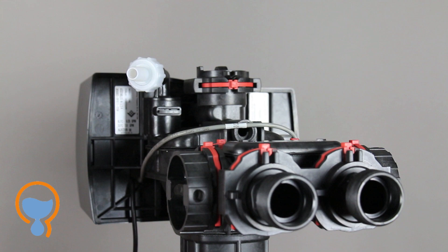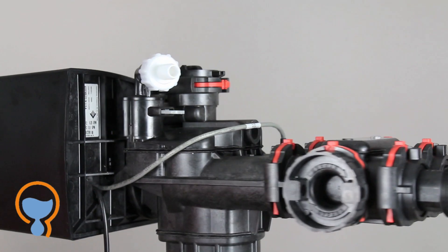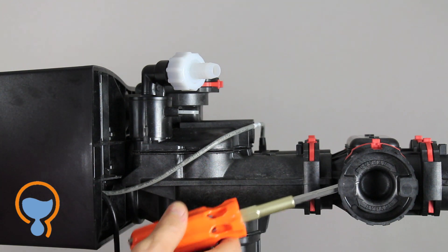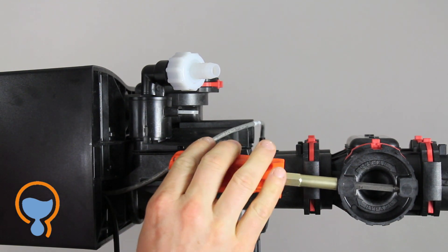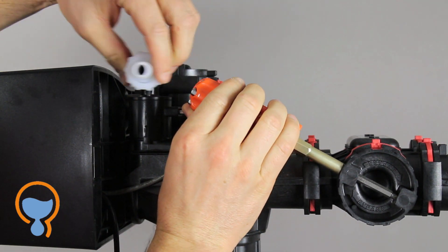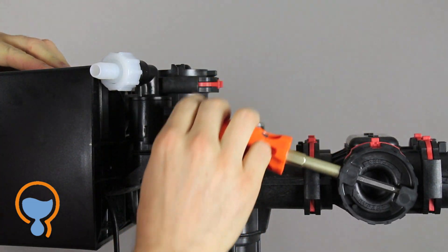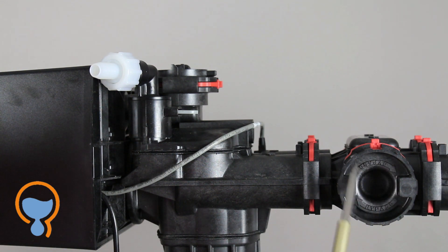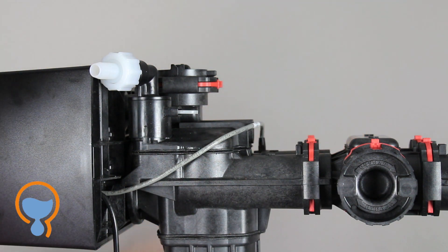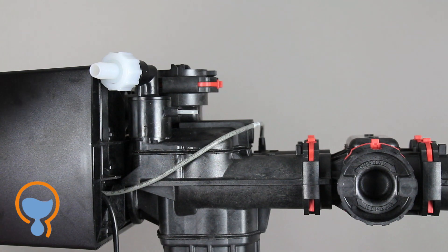On the side of the bypass valve, we've got the actual bypass mechanism. There's little holes for a screwdriver, and you can push and twist in and out of bypass mode. Each of these ports is controlled separately by one of these little dials. You've got one here, and then you've got one on the back side here that you need to open and close to put the unit in and out of bypass.